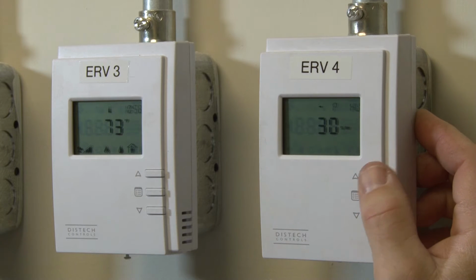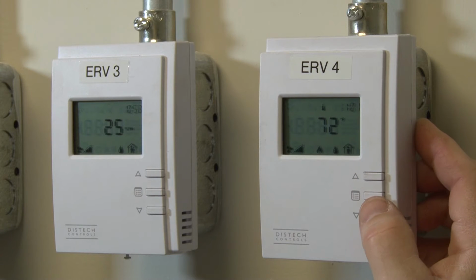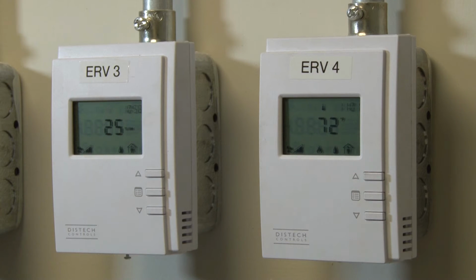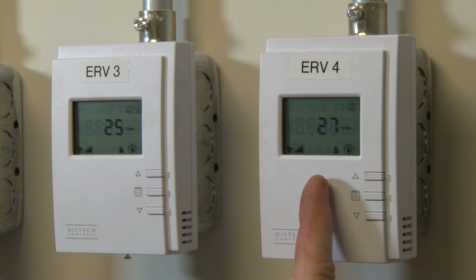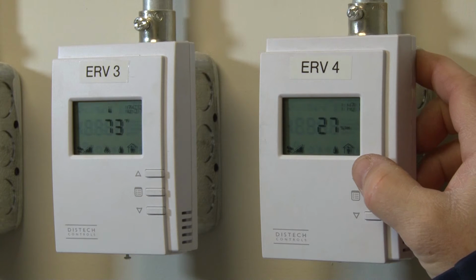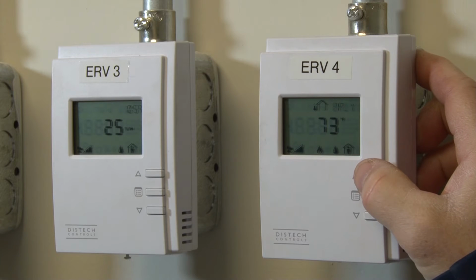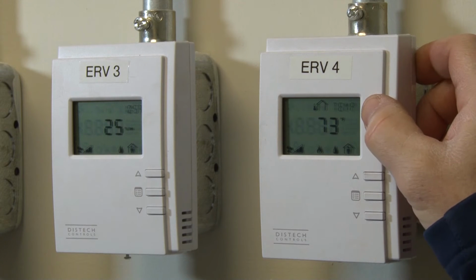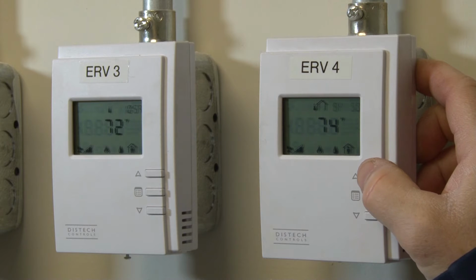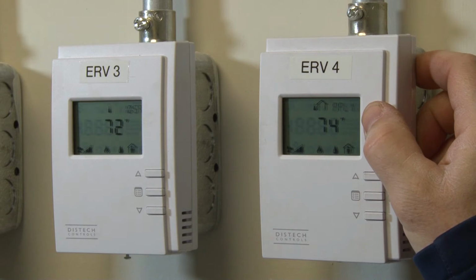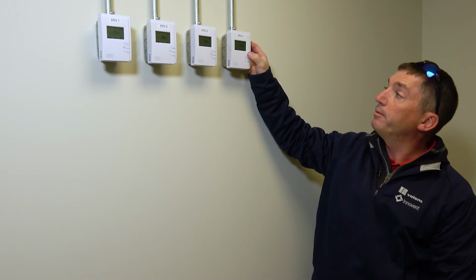To make any modifications, you're going to use the up or down arrow. And if you want to change your supply temperature, you can do that once you're not in that menu. If I come back, wait till the temperature is on the home screen, you'll see in the top right-hand corner it's actually going to change, and it's saying that you're now adjusting the supply set point.